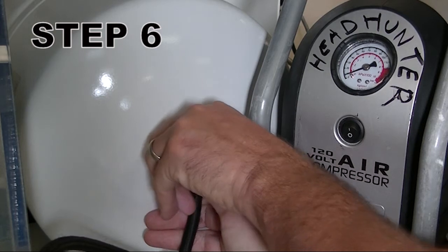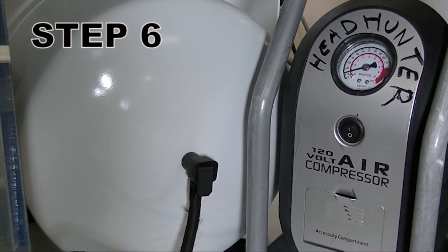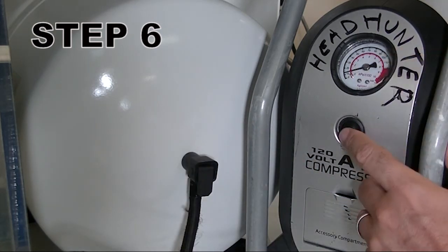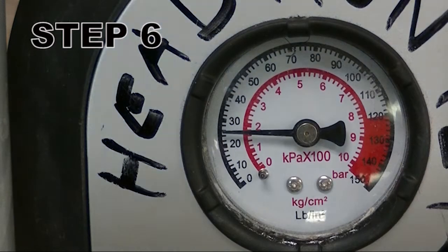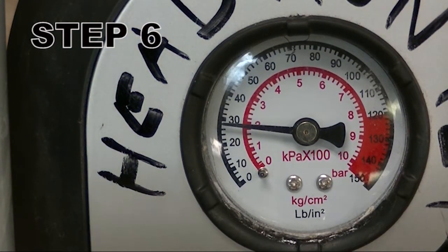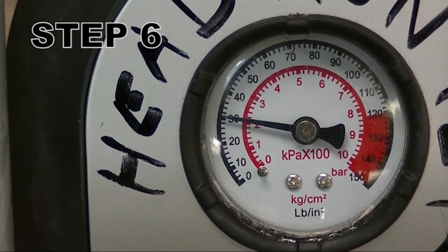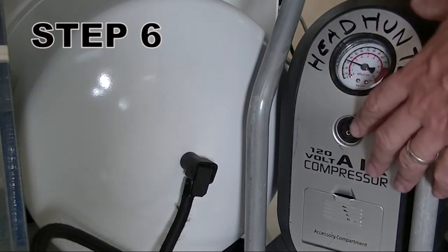Once water pressure is relieved, check the air pressure in the accumulator tanks. The air pressure should be between 30 and 35 psi. Recharge the accumulator tank if needed. If tank does not hold air, then the accumulator tank needs to be replaced.